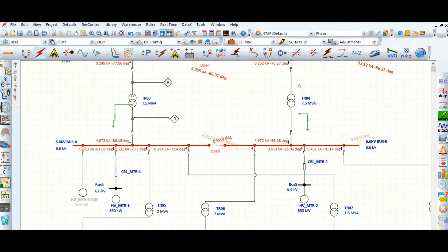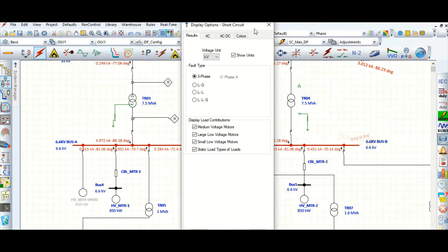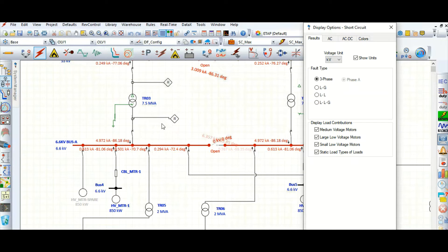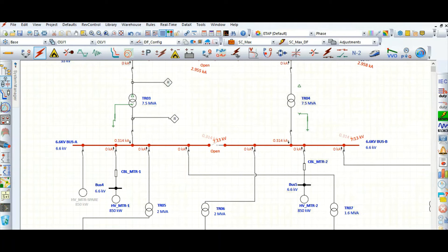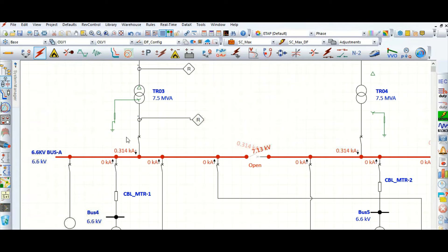Go to the display option. It is currently showing the three-phase short circuit current. If you select line to ground, you can see the result is coming as 0.314 kA. This is 314 amperes because we have limited the ground fault current to 300 amperes.